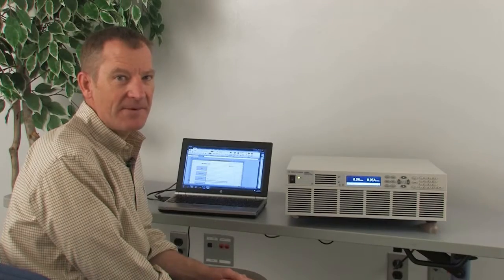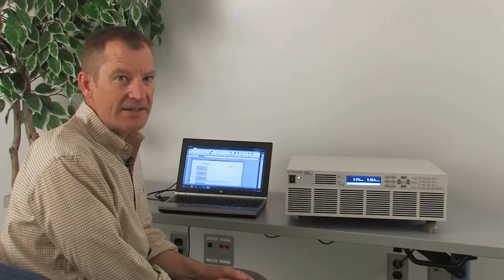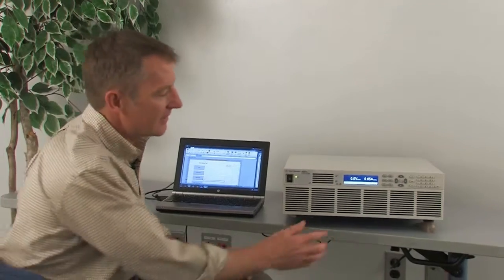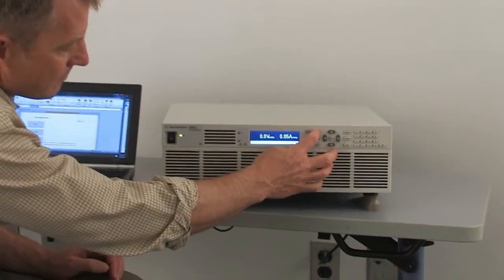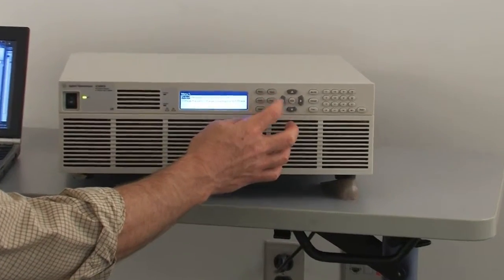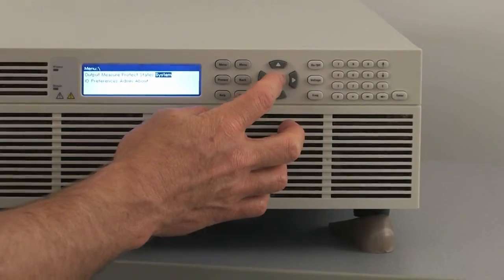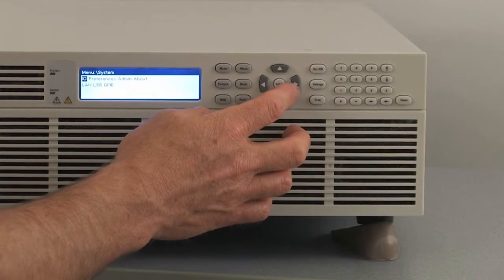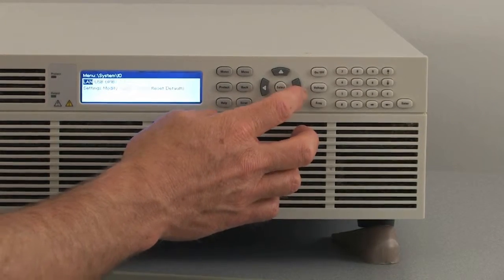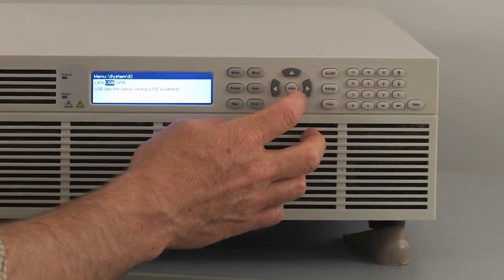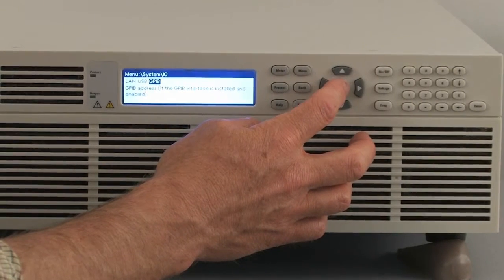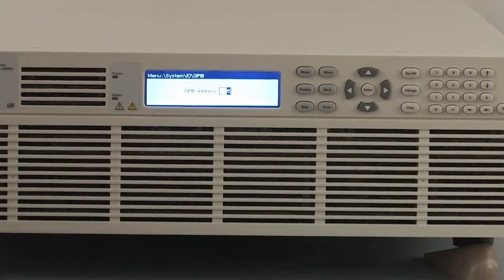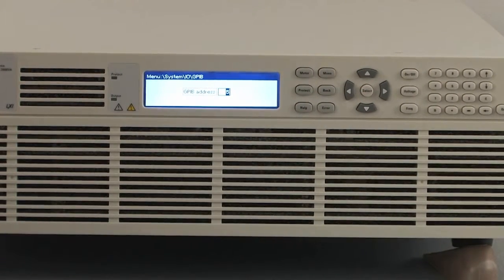With the optional GPIB interface installed, we can go ahead from the instrument front panel and see the interfaces using the system menu. We can read off all of the instrument addresses and we'll look at the GPIB address and it's set to the default address of five.